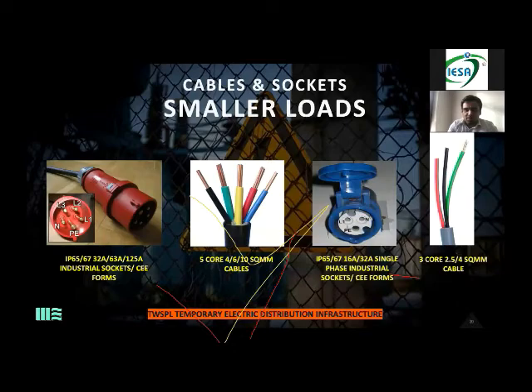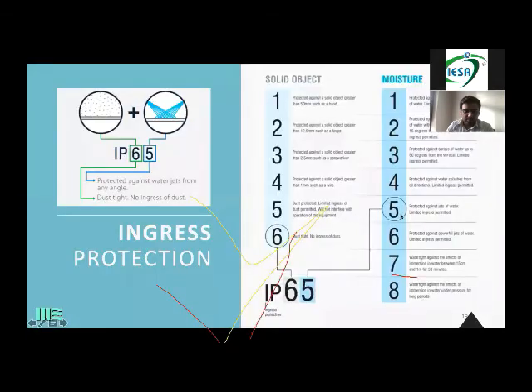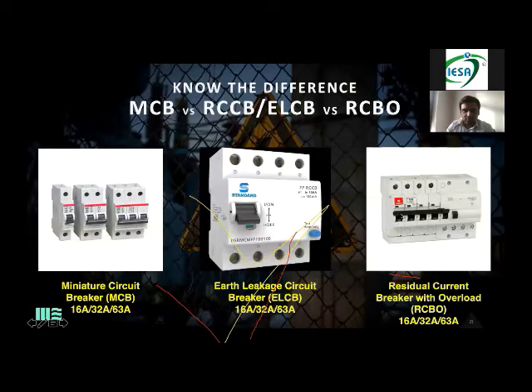Where can that 30 kilowatt load be used? I'll give you an example. Your ACs: if your 8.5 ton AC is coming, you multiply it by 1.75, and whatever the kilowatts come, the same size of wire and the same size of socket has to be used, and the same size of MCB or ELCB or RCBO, whatever your vendor is using or whatever you ask for, has to be used for it.